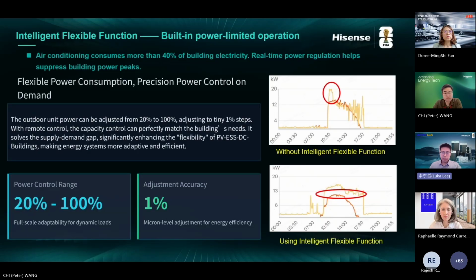You can see in the two figures: without the intelligent flexible function, the unit will run to maximum power consumption and capacity, causing a peak, after which the unit may work with voltage vibration. If using the intelligent flexible function, the power consumption is much more stable.